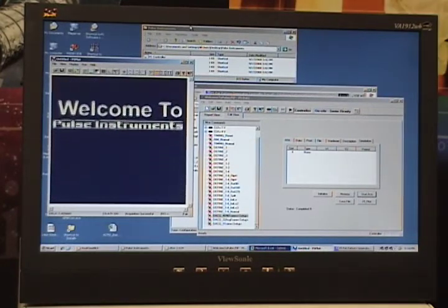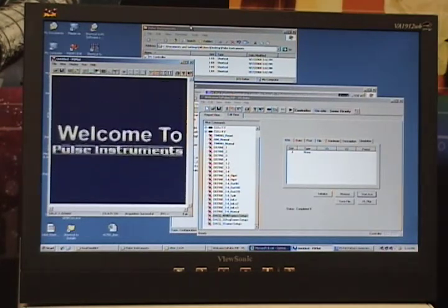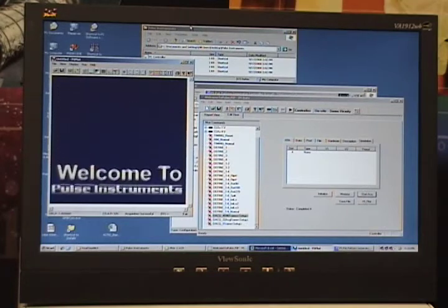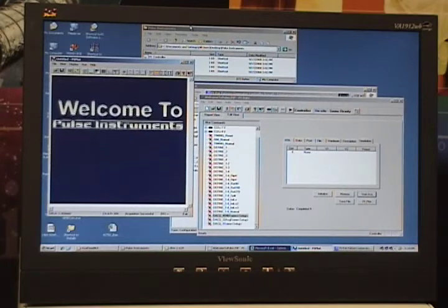Even if your device reads out continuously, as many focal planes do, you will not drop any pixels or any frames using our system. You can collect all your reference rows and columns, which can be very important when doing frequency domain noise analysis.